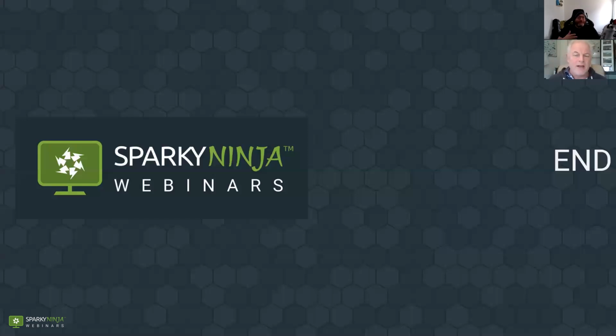Maybe. So I honestly think the IET and the powers that be are playing catch up with this, and technology is so new. The technology is changing so quickly and so rapidly. They're still thinking about ideas. I was looking at also this business of 722.411.4.1, which talks about PME system should not be used. It doesn't say change it to TT there. It says that you put an earth electrode in alongside your PME. And then when they're talking about if you do change to a TT, you've got to look at your electrical separation of your earth from the exposed conductive and extraneous conductive parts.